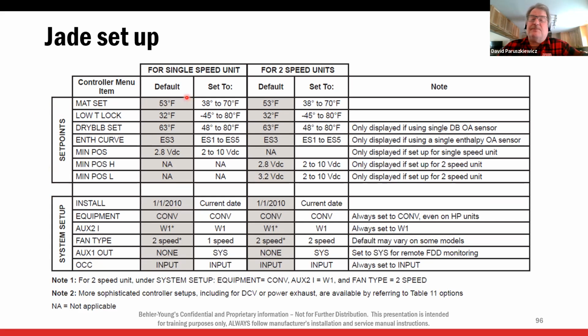So mixed air temp. Remember, that's what controls outdoor air dampers so we don't get too cold into the space. My mixed air temperature factory default is 53 degrees. I can change that. Why would I want to change that? Well, maybe this is a factory. I don't care if the mixed air is colder, and I've got a little heavier load, so I want a little colder air coming in. Well, great, then we can change it from 38 to 70. I can change my mixed air.